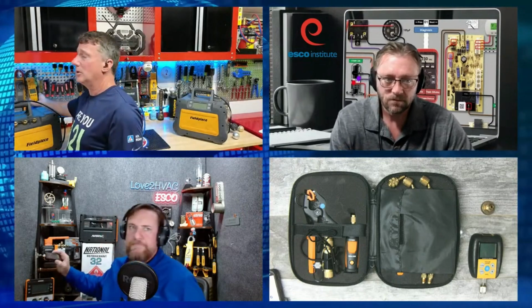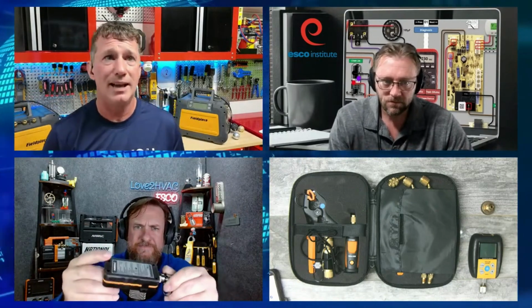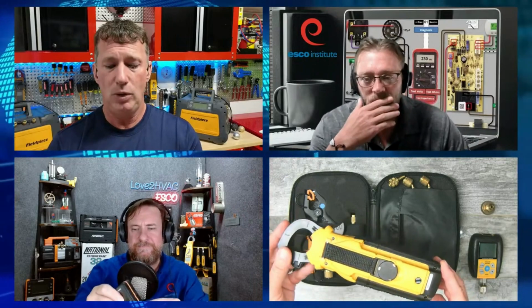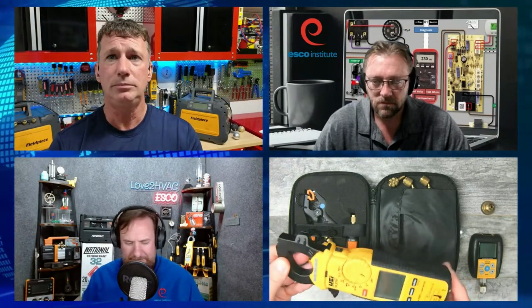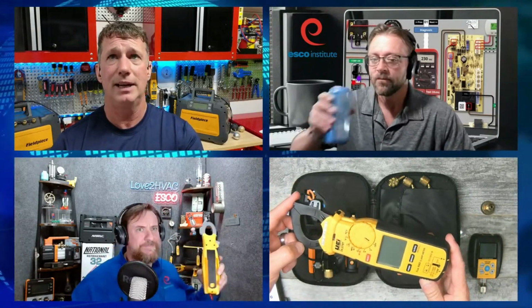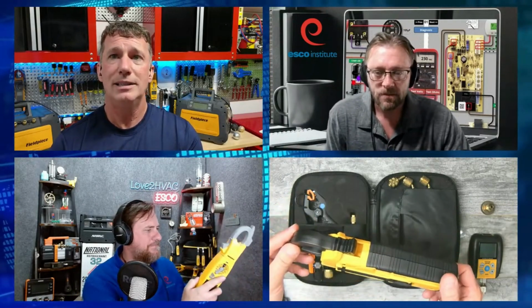But what if a tool manufacturer takes an existing meter that didn't have an A2L compatible sticker on it the year before and they go, oh, by the way, when we redesigned this a couple of years ago, we already went with a sealed electrical compartment that is water resistant and is non-incendiary. Do I need to send this meter off for a $30,000 certification? Probably not going to happen. So when they're evaluated to standards, the tool manufacturers are able to call them A2L compatible based on national standards, not to a specific certification.